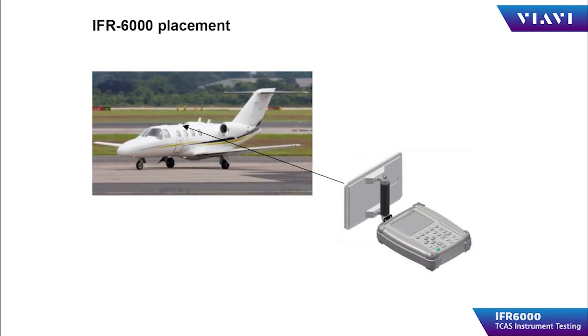A location for the IFR 6000 should be chosen so that there are no metallic obstructions between the IFR 6000 and the aircraft TCAS antenna. The TCAS antenna should be in clear view of the operator's IFR 6000 flat plate antenna. Be aware of any hangar walls, toolboxes, or other aircraft near the aircraft you are testing, as these can cause reflections and multipath interference while testing.